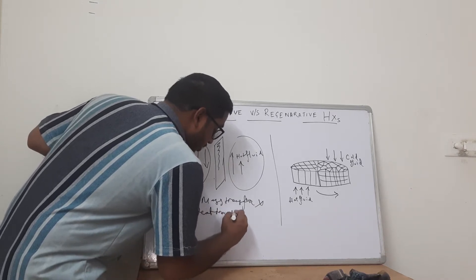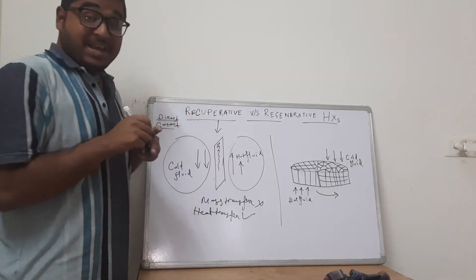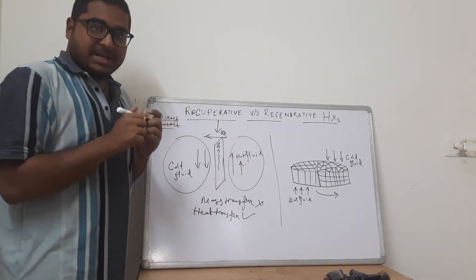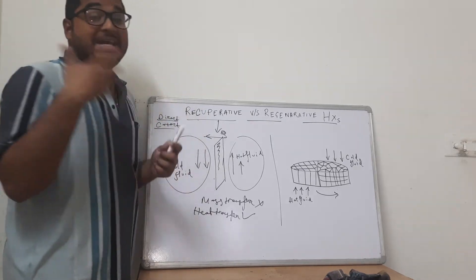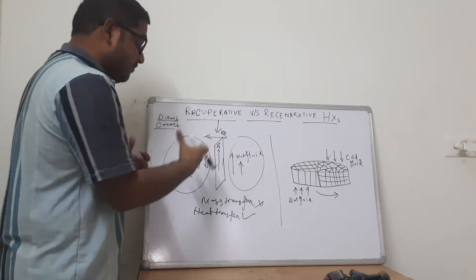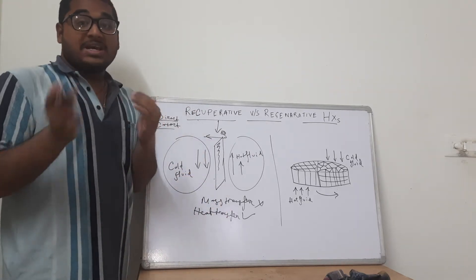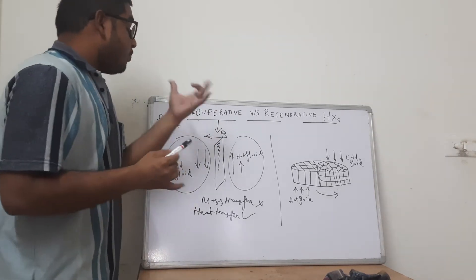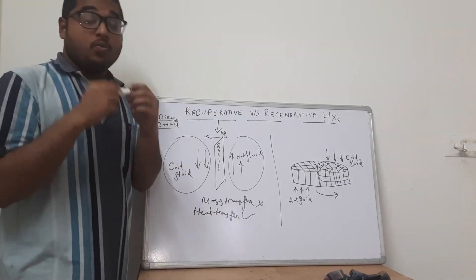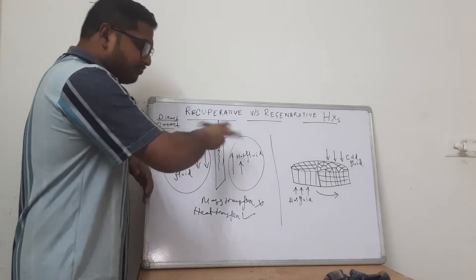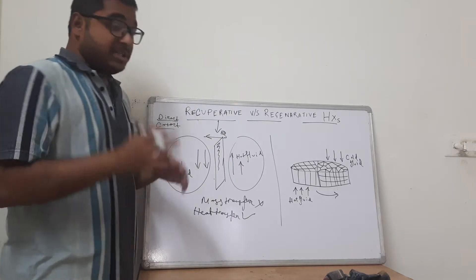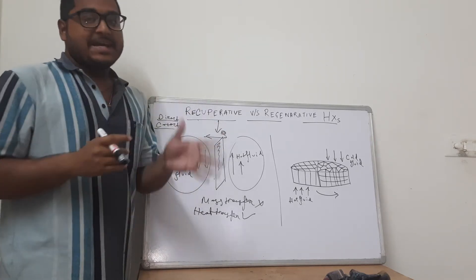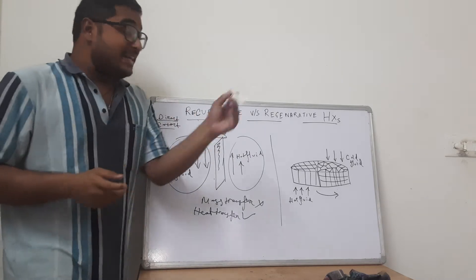In a recuperative heat exchanger, we must ensure that the conductivity of the plate is very high so that a large amount of heat can transfer from the hot fluid to the cold fluid. The heat transfer depends on the heat exchange surface. Direct contact heat exchangers are much more effective when it comes to heat exchange because there is no barrier. The definition of recuperative heat transfer is: a heat transfer method in which the hot fluid and the cold fluid flow simultaneously — anti-parallel or parallel — with the heat exchange surface in between, such that the hot fluid never comes in contact with the cold fluid and only heat exchange occurs.